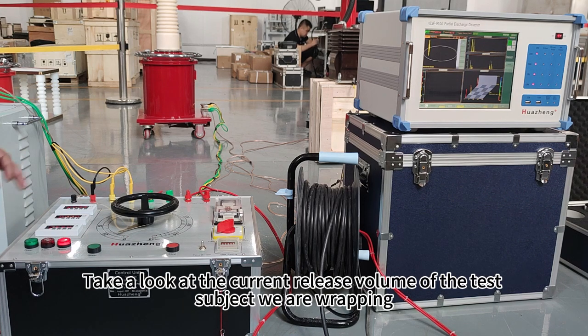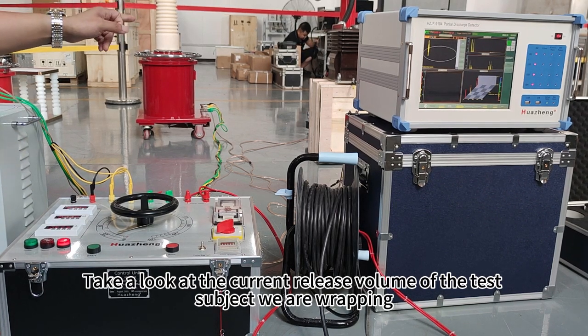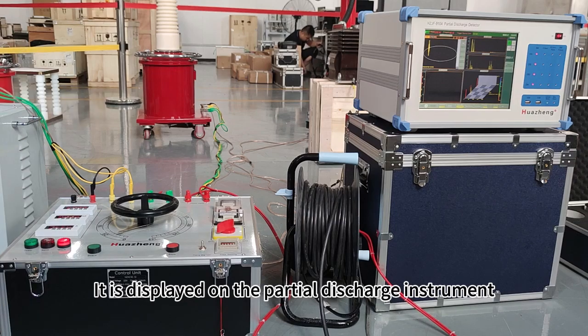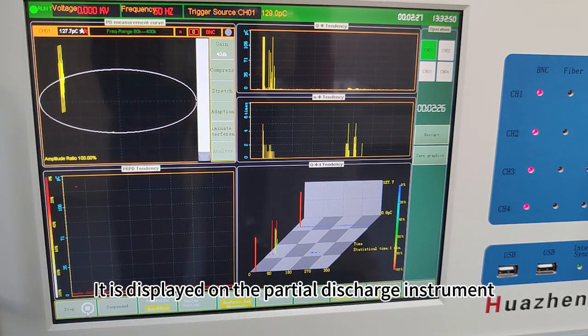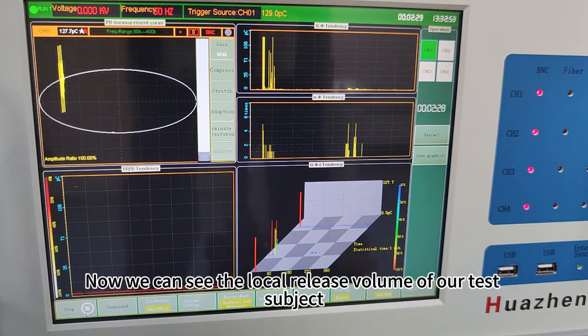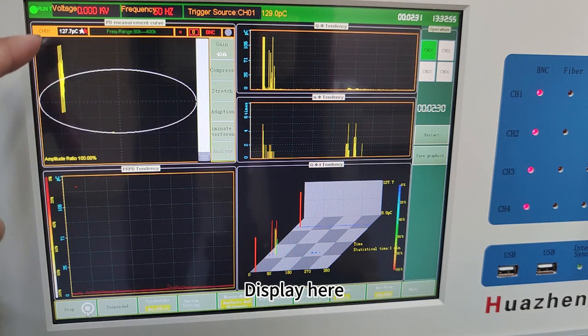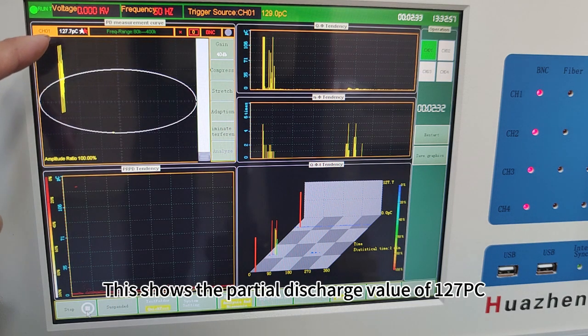Take a look at the partial discharge volume of the test subject we are raising. It is displayed on the partial discharge instrument. Now we can see the partial discharge volume of our test subject displayed here. This shows the partial discharge value of 127 pC.